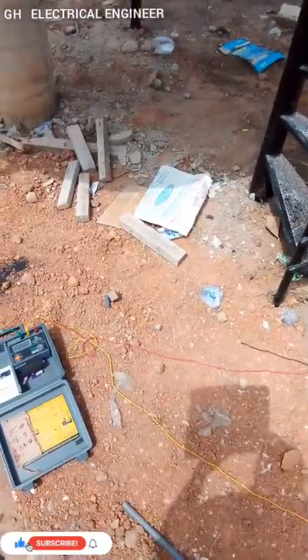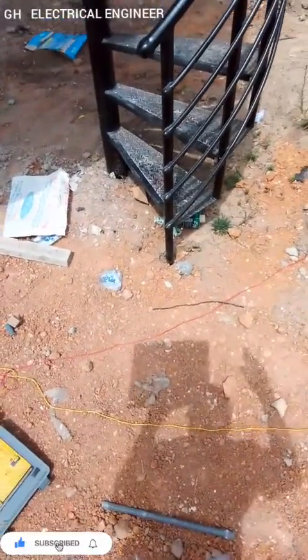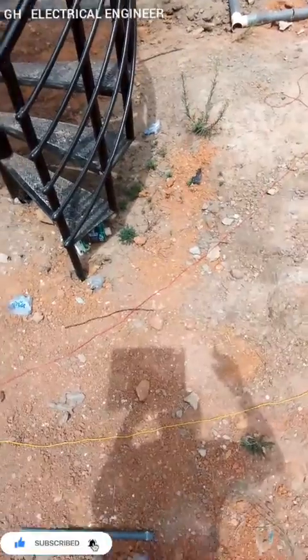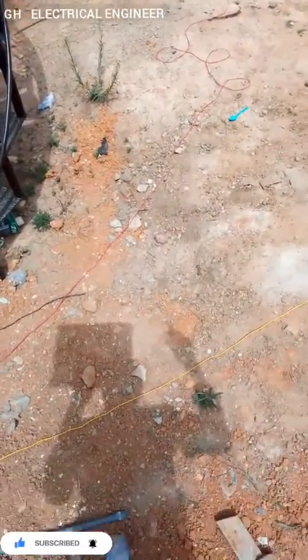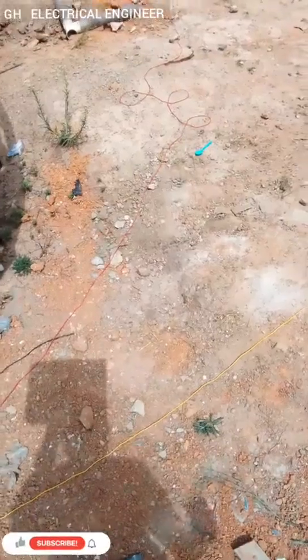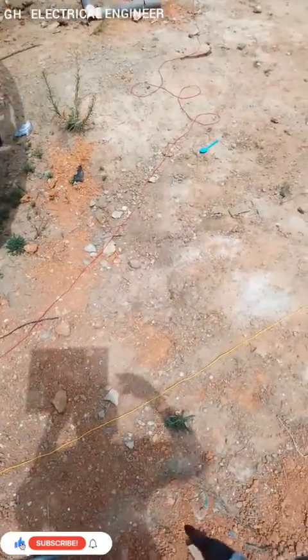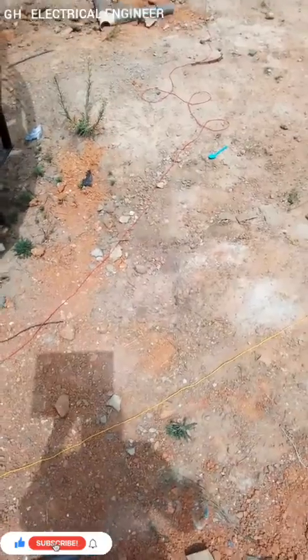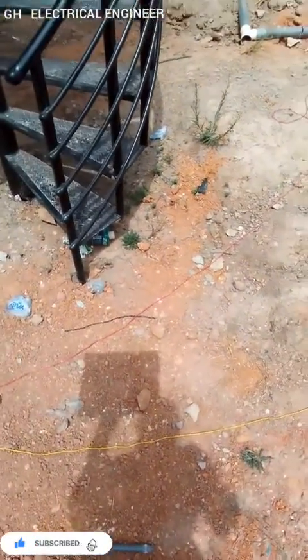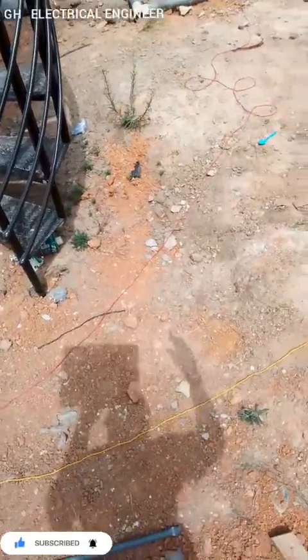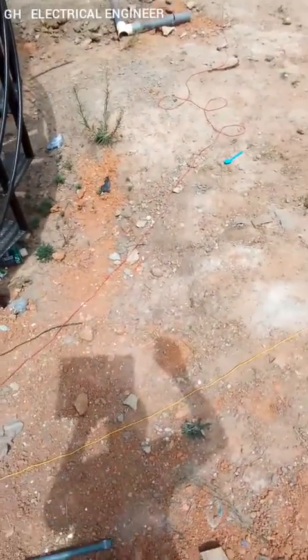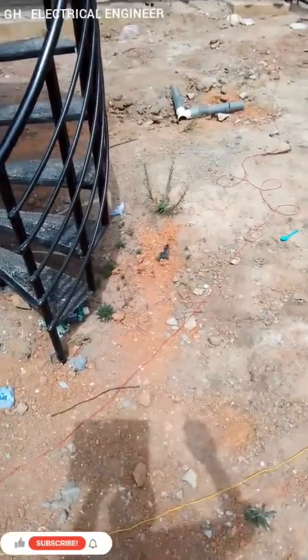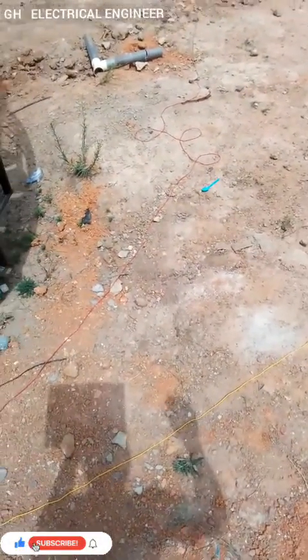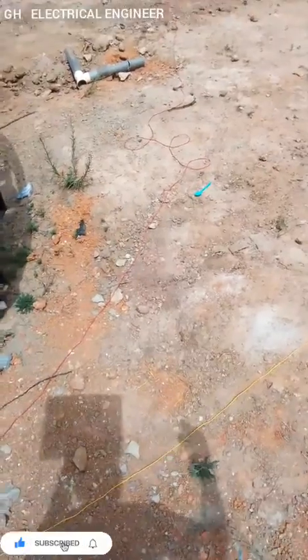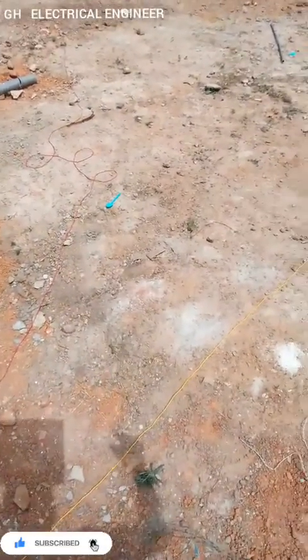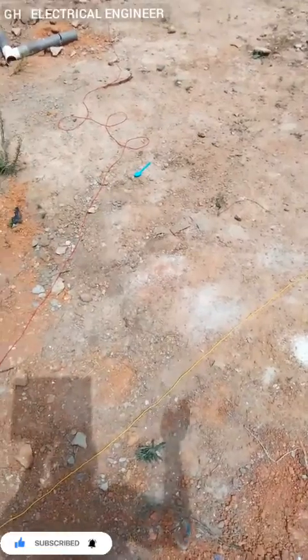The earthing system has to be checked periodically because it can lose its low ohms, and the resistance can become high. That is why we test it on a very dry day, because testing on a rainy day gives a falsely low ohm reading, which isn't accurate. We test on dry days because we want what's good for our client. We cannot risk their life, that's why they need a good earthing system.